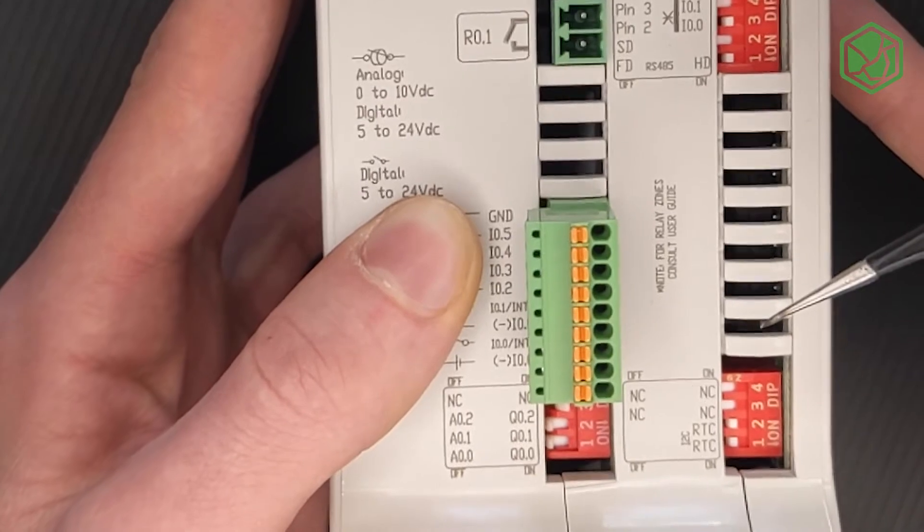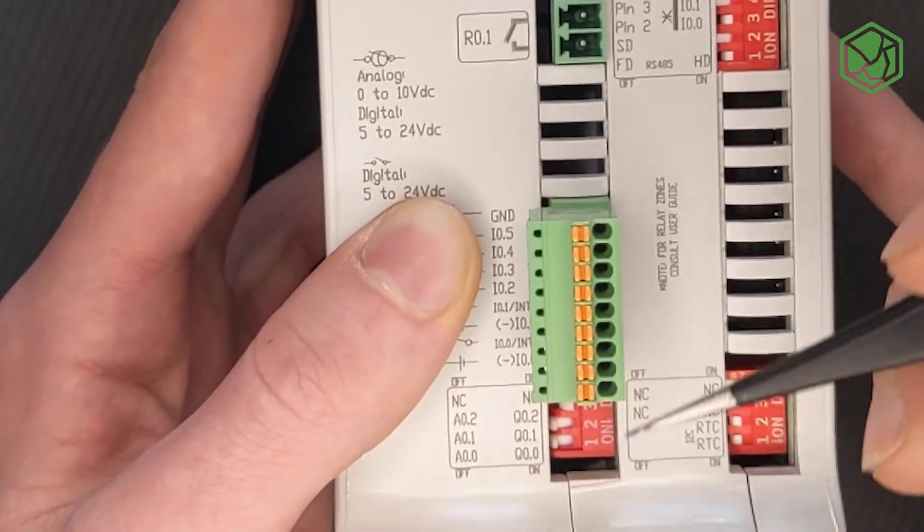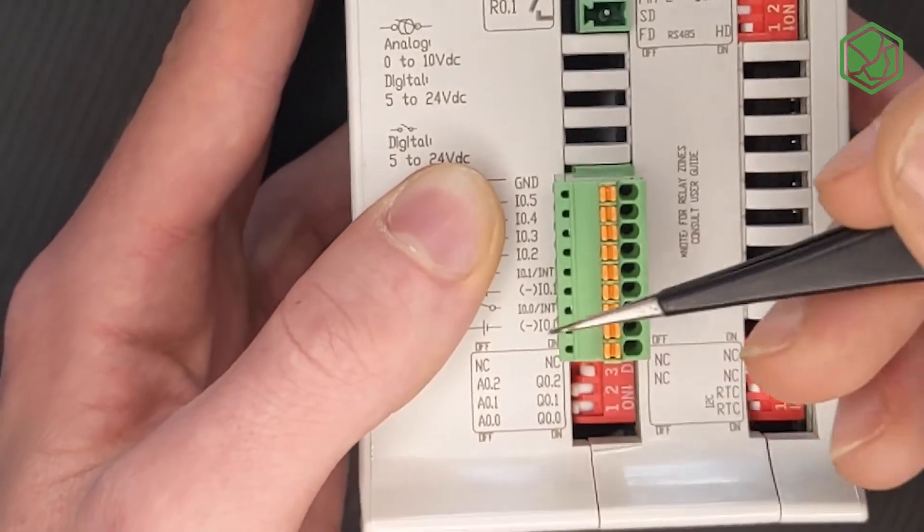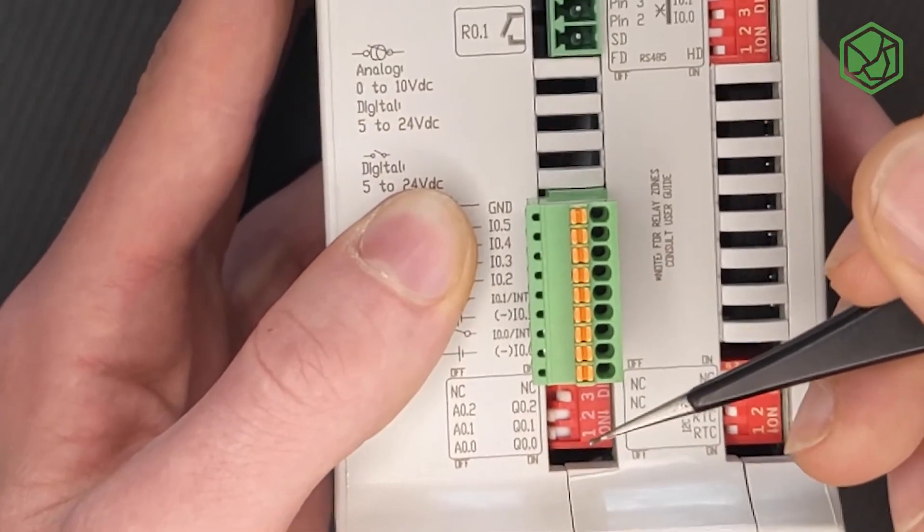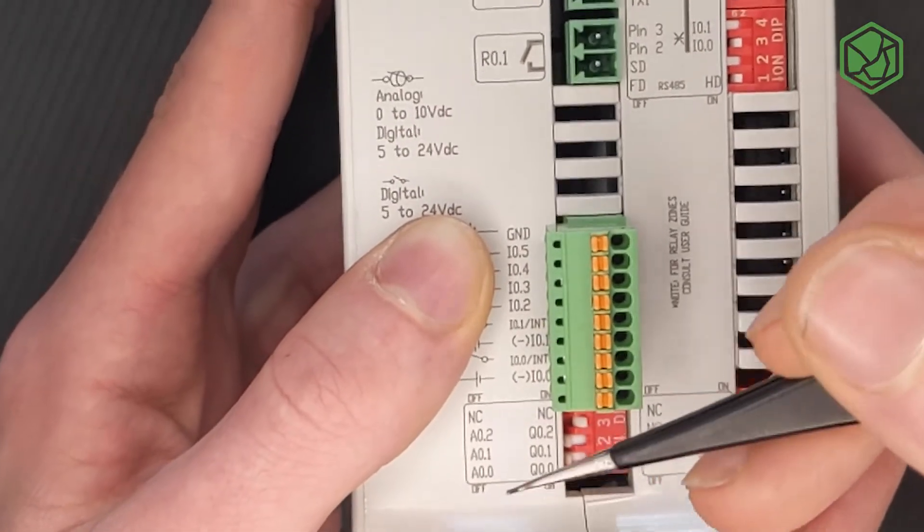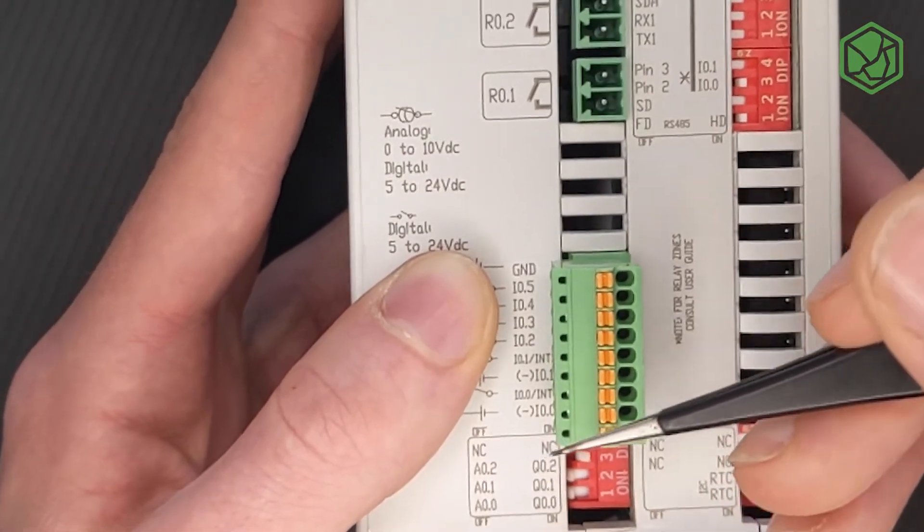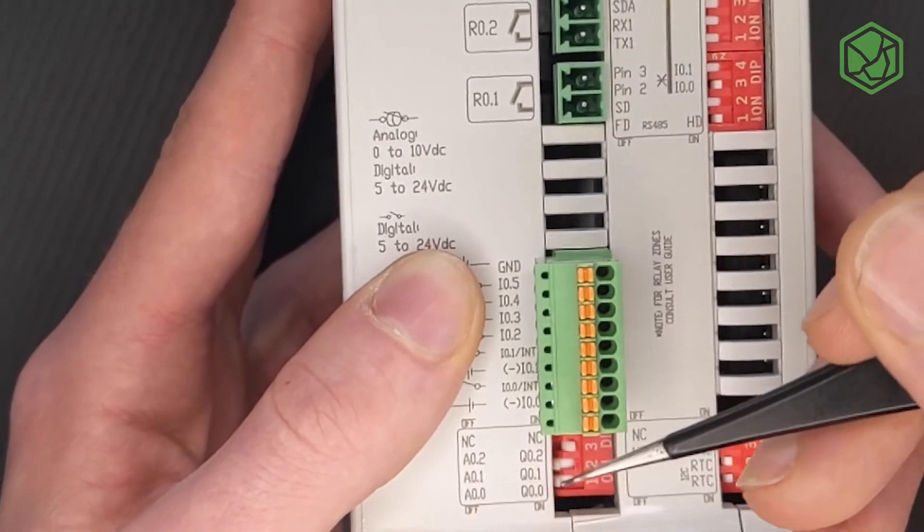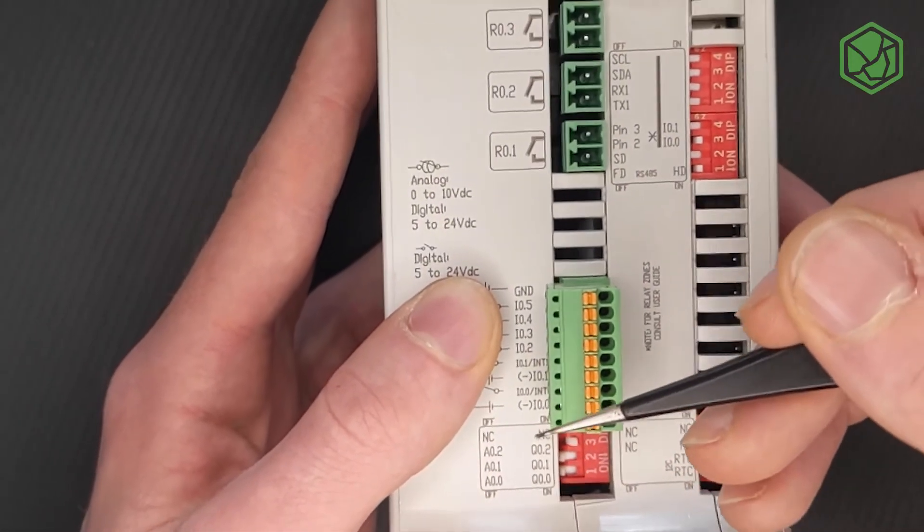Finally, respect the DIP switch, the switches 3, 2 and 1 must be configured individually to off position if you want these outputs to work as analog outputs or to on position if you want each one to work as digital output.